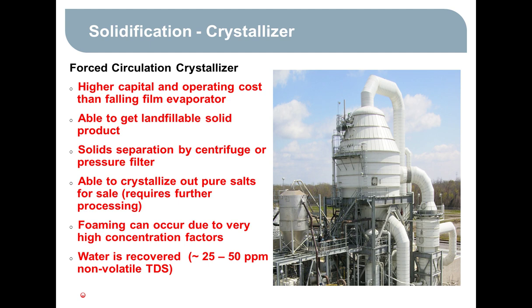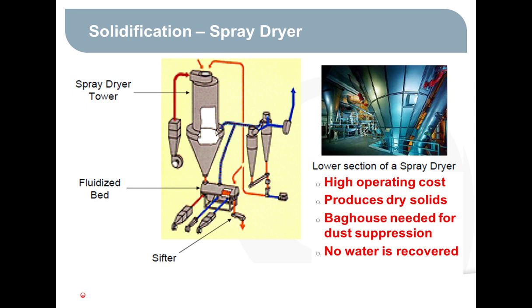Spray dryers, I'm not going to talk about spray dryers very much, but spray dryers are another thermal method of achieving solidification in a ZLD scheme. The problem with spray dryers is that unless the waste heat is free or very low cost, spray dryers are quite inefficient. It takes about 1,000 BTUs to drive off a pound of water in an evaporator, but it takes almost twice or 2.5 times that in a spray dryer, just because spray dryers are very inefficient in terms of heat transfer. So unless that energy is free or very, very low cost, spray dryers are usually not very economic.